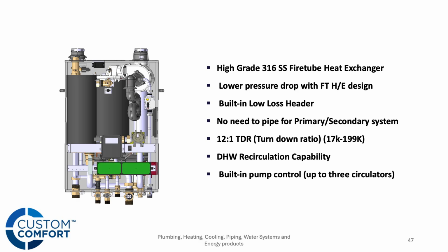Also on the boiler is a built-in pump control. So the control board of this boiler has the ability to control and power up to 3 circulators. So anything less than 3 zones, we don't need an external relay or circulator control, right? We can do that all based on the control board of the boiler itself. So again, you're saving some money without the need for an external control if you have less than 3 zones.